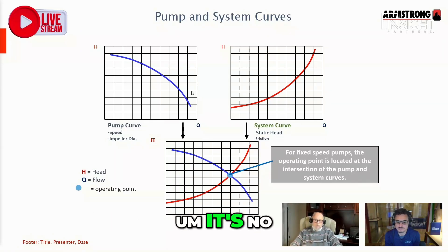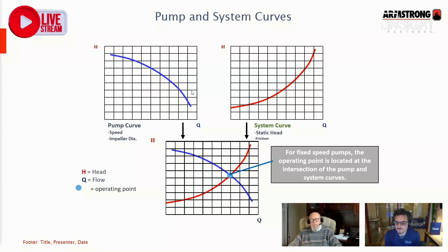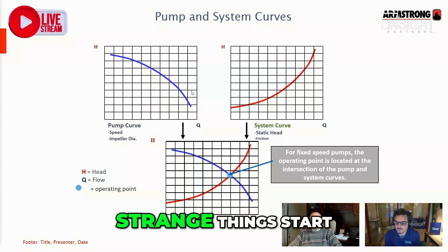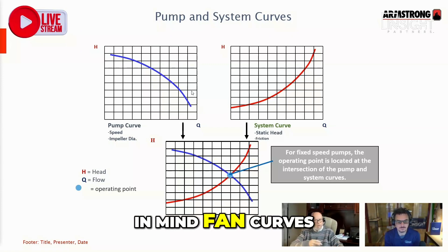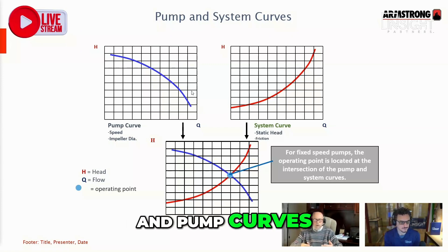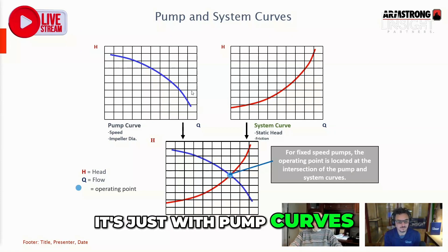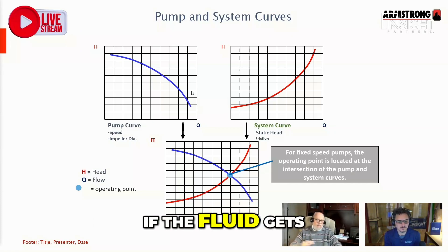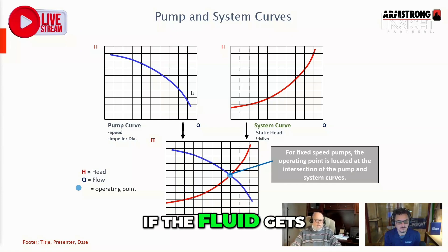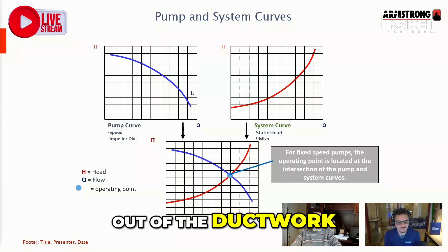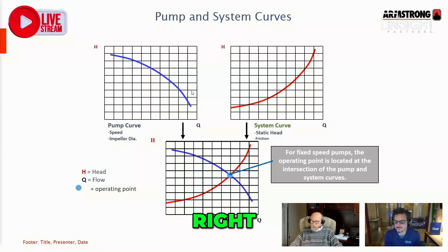And it's no different than a fan curve. When you get to the end of the curve, strange things start to happen. So keep in mind, fan curves and pump curves — we're moving a fluid. It's just with pump curves, if the fluid gets out of the pipe, you get wet. In a fan system, if the fluid gets out of the ductwork, you just get blown on.